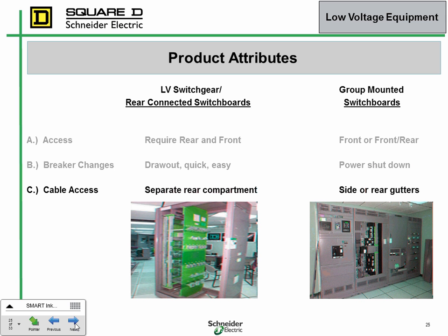So again, depending on the piece of gear, there are many options for barriers. You could have side barriers in the cable compartments, side barriers in the bus compartments, and barriers between the cable and bus compartment. If you apply all of those, then when somebody goes into the back and opens that door, all they're going to be exposed to are the load cables from that section. So if all the breakers are opened in that section and you open it up, everything should be dead back there.